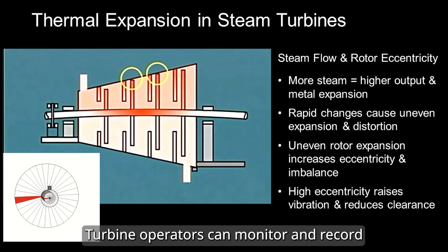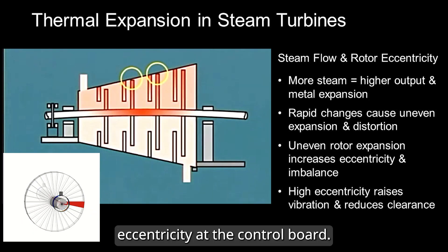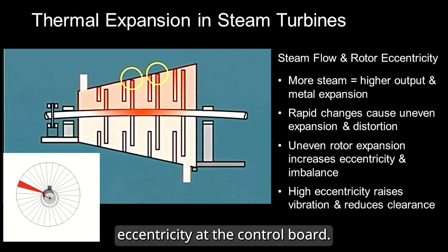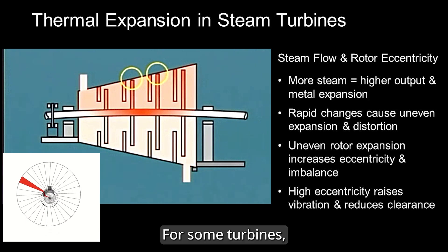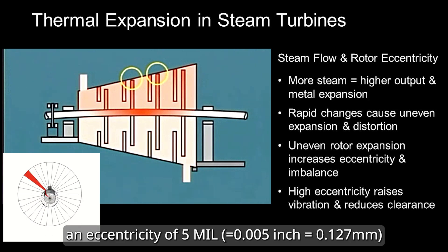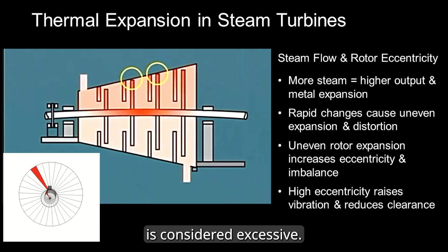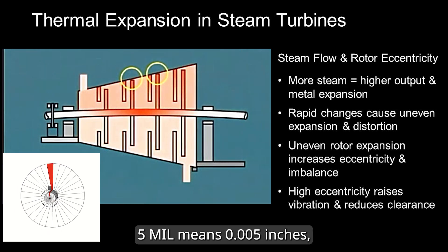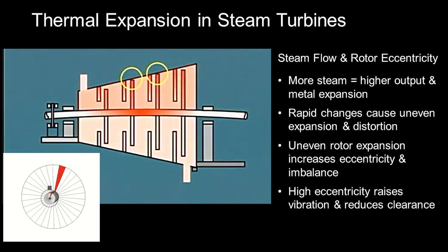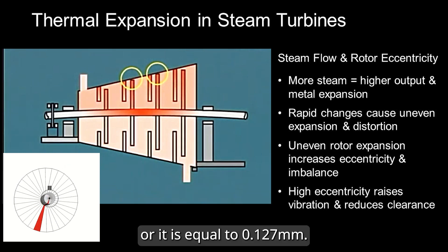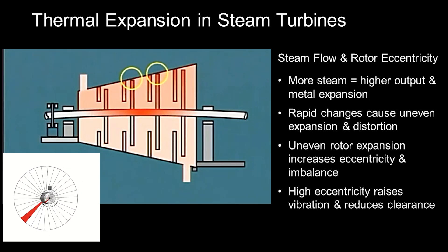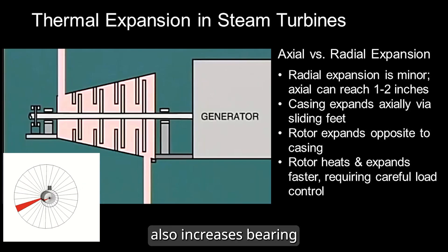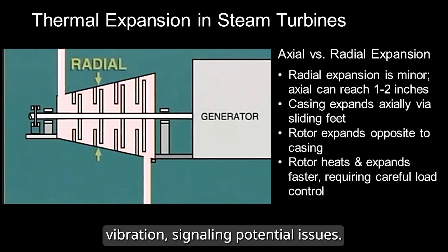Eccentricity is dangerous because it reduces radial clearance between rotating and stationary components. Turbine operators can monitor and record eccentricity at the control board. For some turbines, an eccentricity of 5 mils is considered excessive — 5 mils means five thousandths of an inch, or 0.127 mm. High eccentricity also increases bearing vibration, signaling potential issues.